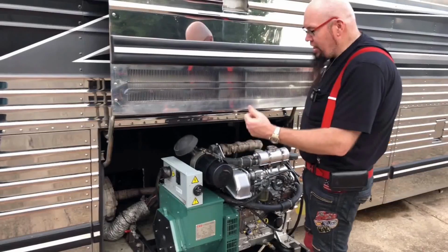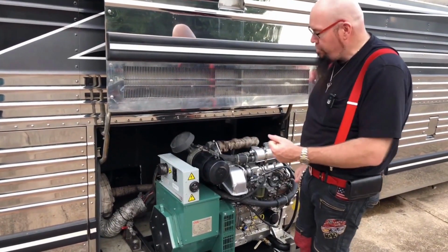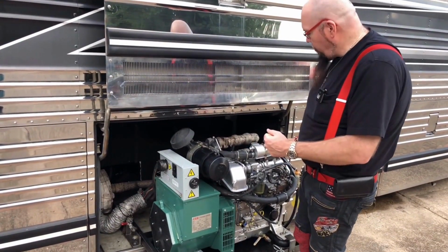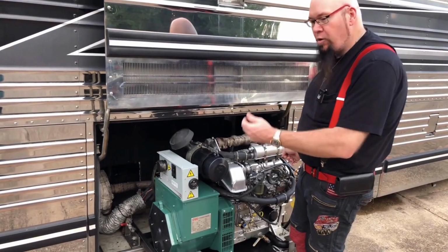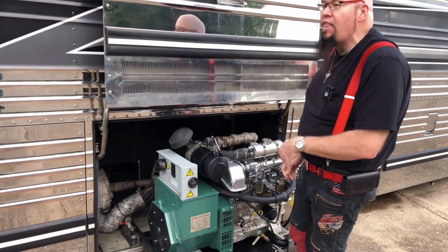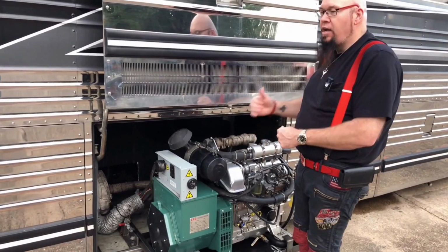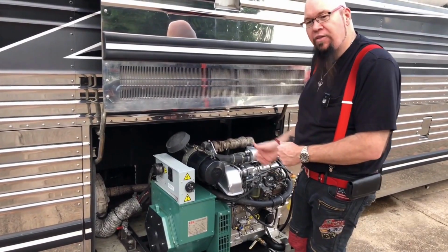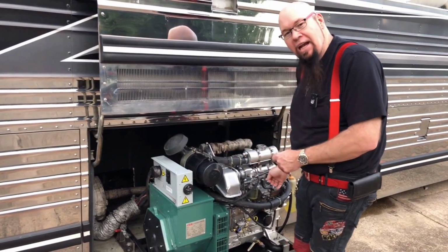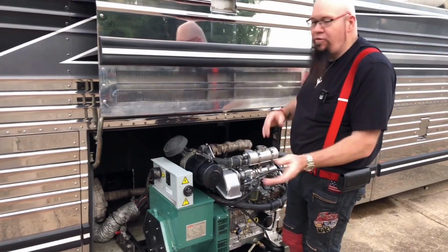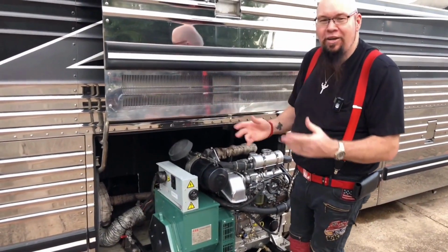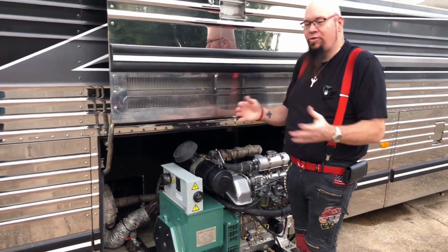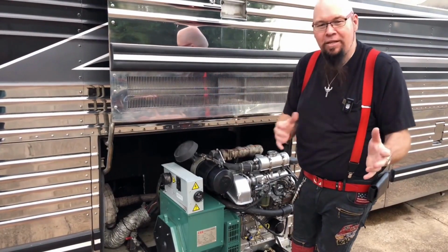Once you've installed the unit and it's running and outputting power, turn your RPMs up to just the point where you're getting the correct hertz you want. Then turn on everything you can, put the biggest load on it that you can, and see what your hertz are. You may need to add a little RPM for that. If you're a few hertz higher or lower, it's not going to kill anything. Running 62 hertz or 59 isn't going to make that big a difference.